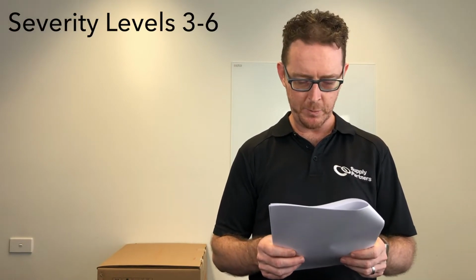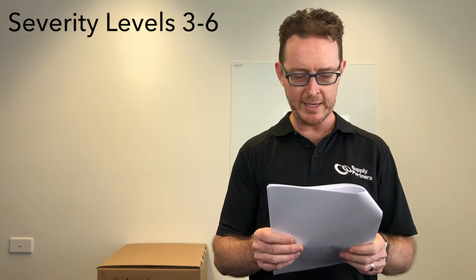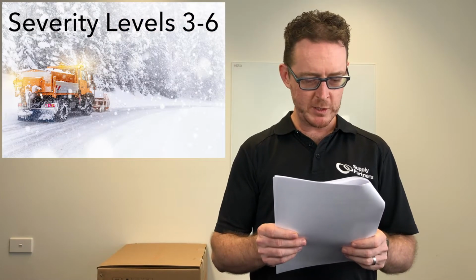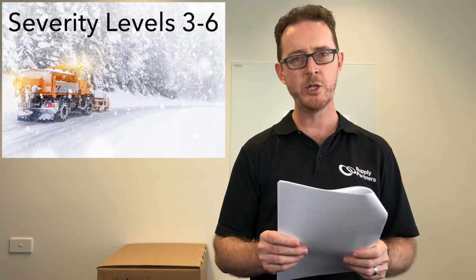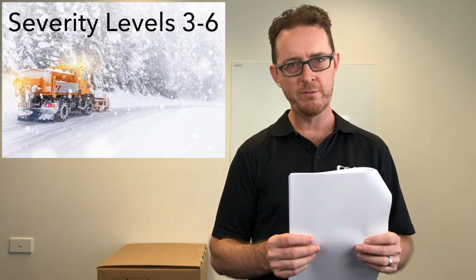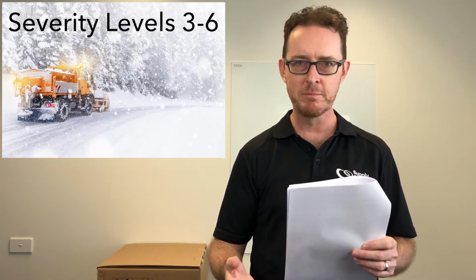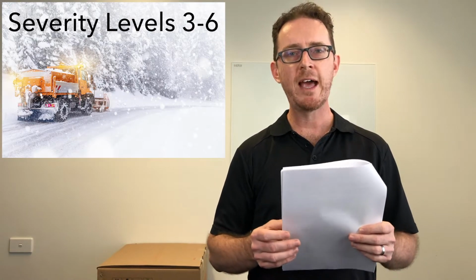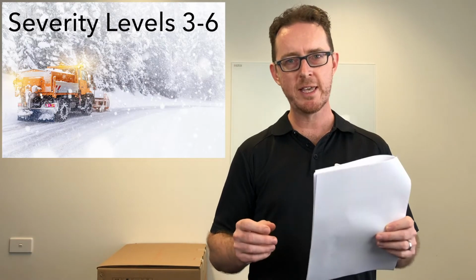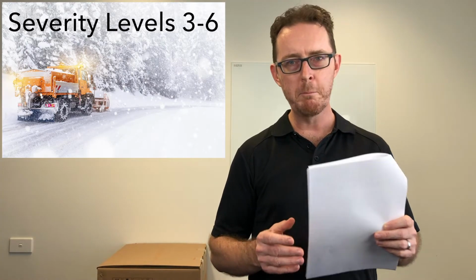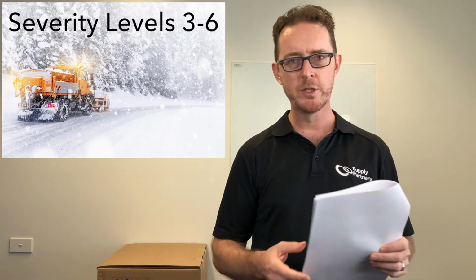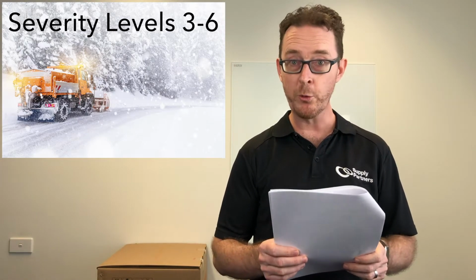It goes on to say severity levels 3 to 6 are intended for PV modules operating in locations where there could be a change between salt-laden air and dry atmospheres. For example, in places where salt is used to melt ice formations. So in some very cold environments, Canada, Alaska, Scandinavia, places like this, where they have heavy snowfall, salt can be used on highways to melt the snow to open up the roads. And that's what they're talking about for severity level 3 through 6.